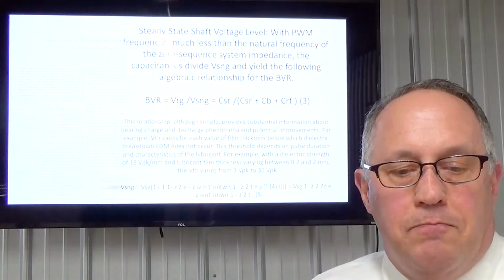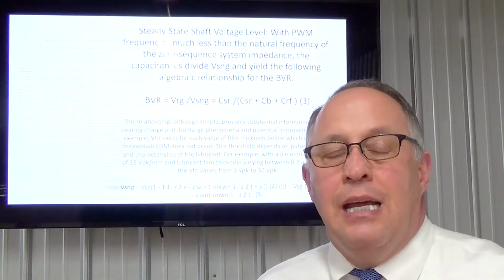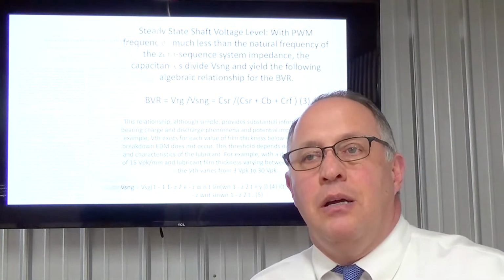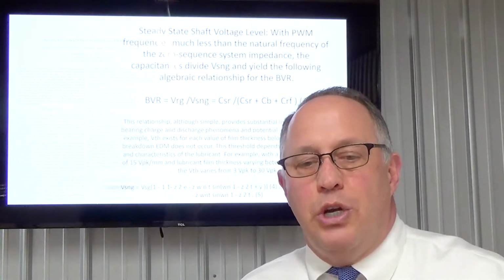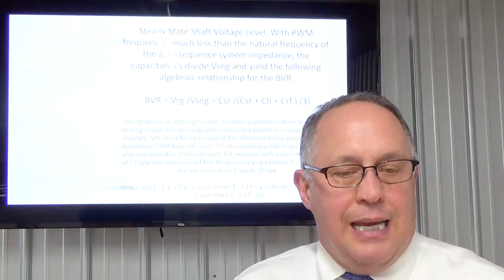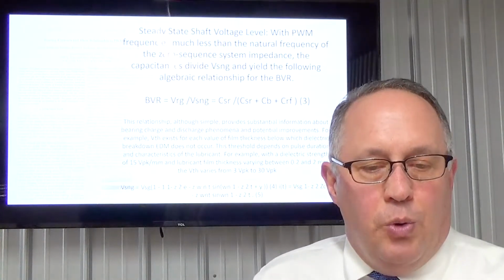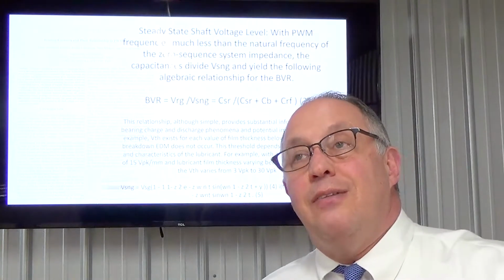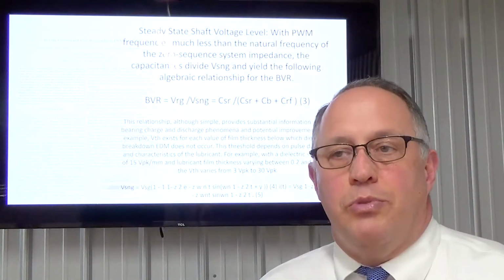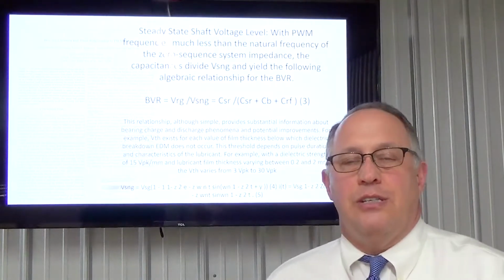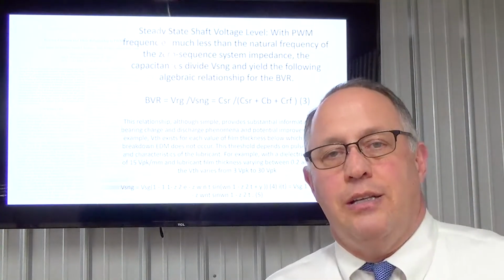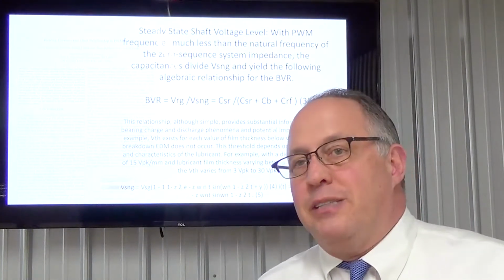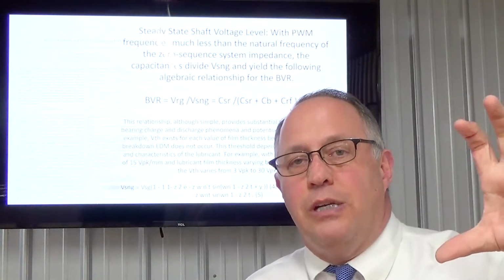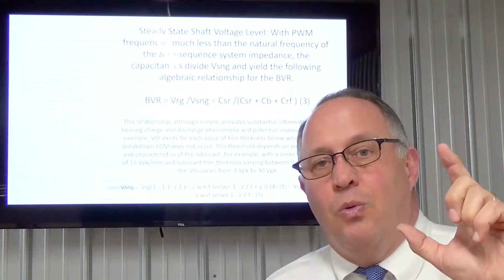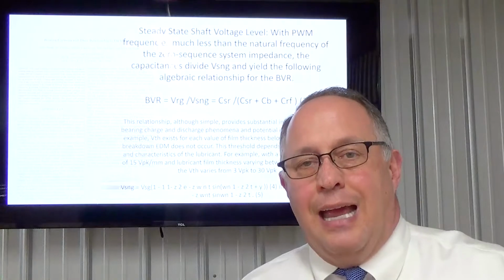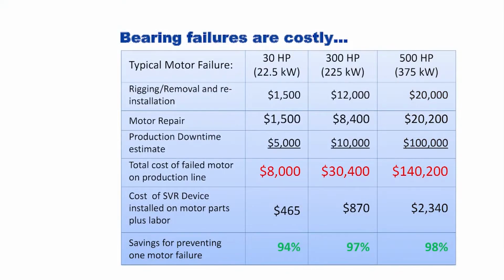The actual calibration of the VFD. Have we gone through the setup, auto-tune function or tuning functions to make sure that it's set up right? Is it properly grounded? Do we have any interference? Do we have, in particular cases, standing waveforms that can be developed at particular frequencies that should be edited out? All those go into this 12 variable equation and spits out an answer of the probability of the voltage that is induced on the shaft. What we want to know is, do we have it and can we get rid of it? That's what's important to us today.